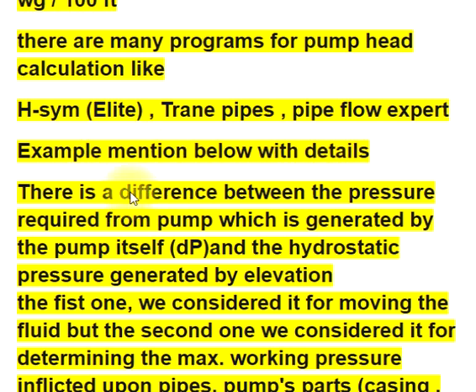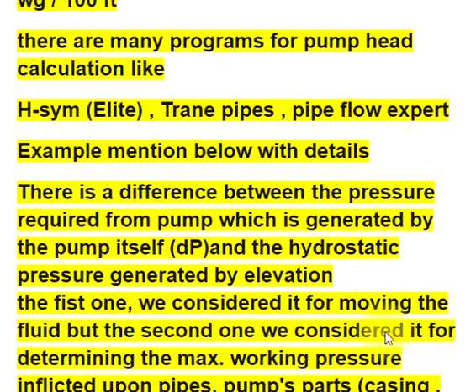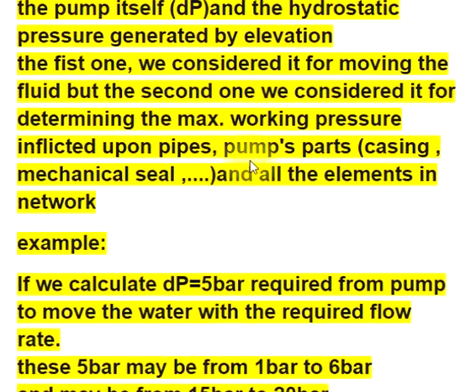There is a difference between the pressure required from the pump, which is generated by the pump itself (DP), and the hydrostatic pressure generated by elevation. The first is considered for moving the fluid, while the second determines the maximum working pressure on pipes, pump parts, casing, mechanical seal, and all elements in the network.